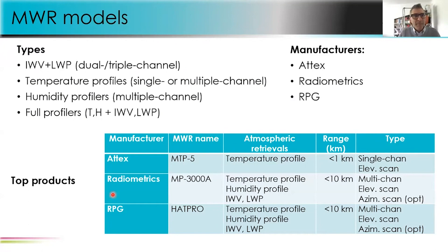The types of instruments available include dual or triple channel instruments to estimate only integrated water vapor and liquid water path, or temperature profilers, humidity profilers, or full profilers providing all products mentioned. The three manufacturers, as far as I know, are Attex, Radiometrics, and RPG. Attex offers a temperature profiler up to one kilometer, single channel with continuous elevation scanning, while both Radiometrics and RPG offer full profilers up to 10 kilometers, multiple channels, elevation scanning, and optional azimuthal scanning.